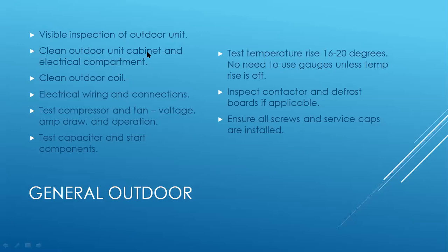So I'm going to clean the outdoor unit cabinet, and then I'm also going to clean the electrical compartment. Nothing's worse than after a tune-up, somebody follows you up and there's a bunch of cobwebs in the electrical box. Doesn't give you the impression that it was cleaned or serviced very well. Also clean the outdoor coil. Depending on what your company's policy is on the outdoor coil, I would definitely clean it of some sort. So depending on what kind of coil it is, you may use coil cleaner, you may use just water, whatever your policy on that is, but ensure that the outdoor coil is clean.